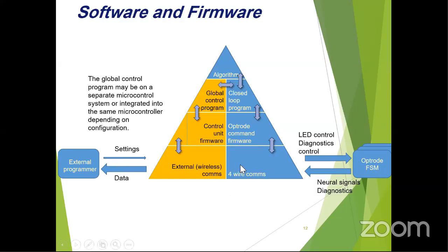First, the 4-wire communication layer to communicate between the control unit and the Optrode. Second is the command layer, if you want to send the stimulate command or the record command—this is a kind of intermediate layer between the user and the Optrodes. Finally, the closed loop program, which does the stimulation and then does the recording.